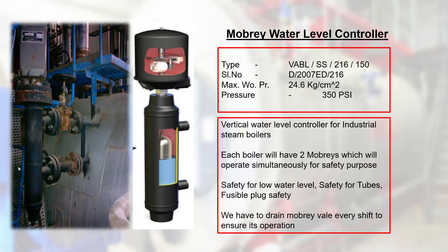Mobrey Water Level Controller: it is a vertical water level controller for industrial steam boilers. Each boiler will have two Mobreys which will operate simultaneously for safety purposes. Safety for low water levels, safety for tubes, and fusible plug safety. We must drain the Mobrey valve every shift to ensure its operation.